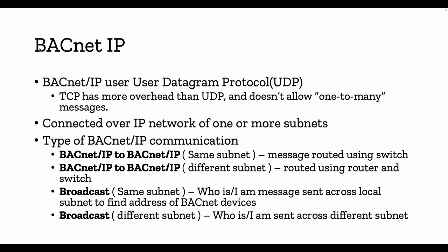Let's drill down a bit into BACnet/IP, since we're focusing on IP-based technologies in IoT. BACnet/IP uses User Datagram Protocol — UDP — not TCP. UDP is a connectionless protocol while TCP is connection-based. UDP is well-supported with many APIs for different operating systems. TCP has more overhead than UDP, so bandwidth and traffic are greater with TCP. Additionally, TCP does not allow one-to-many messages, but UDP supports it — that is one of the main reasons BACnet/IP uses UDP.